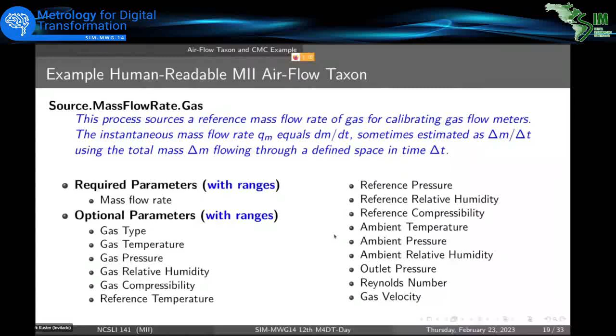And if we look at it in a human readable form, and compare this to, say, airflow CMCs that you see out there in the wild, you'll notice that this has quite a bit more information than you would typically see. Here I've listed not only the range for our CMC with a simplified uncertainty, but also the fact that it's a source, to definitely disambiguate that from a measurement. And we're showing the ranges or default values of all the relevant quantities. The customer may select either dry nitrogen or ambient air. If they don't specify, we'll default to ambient air, 23 degrees C, and 800 kilopascal static pressure, but we have capability over this range, et cetera. So it's much more complete information for searching and using CMCs, and communicating them between organizations.